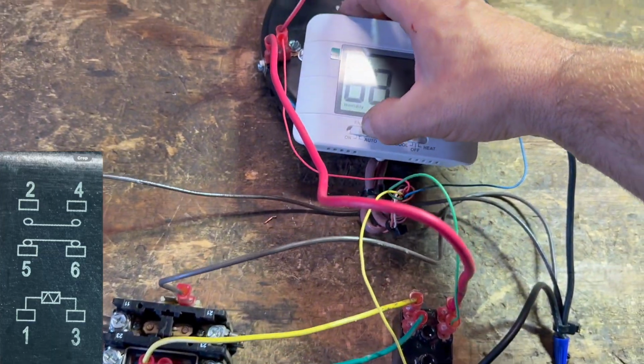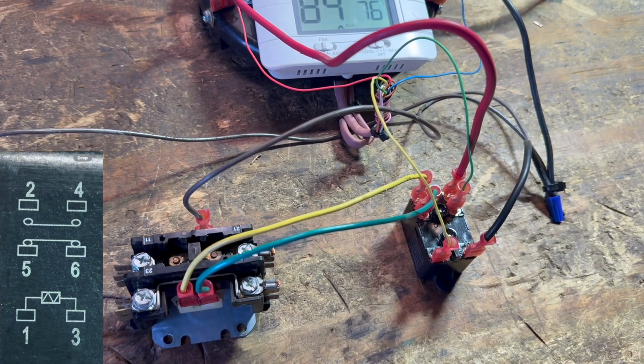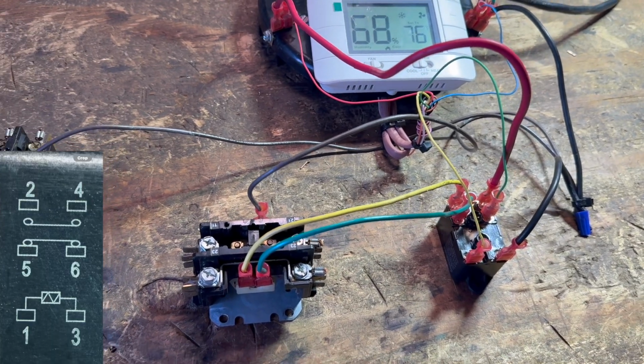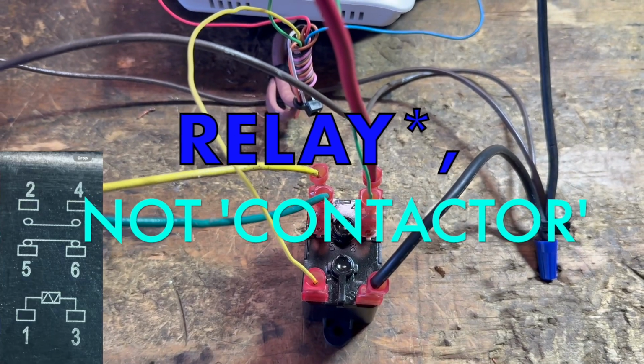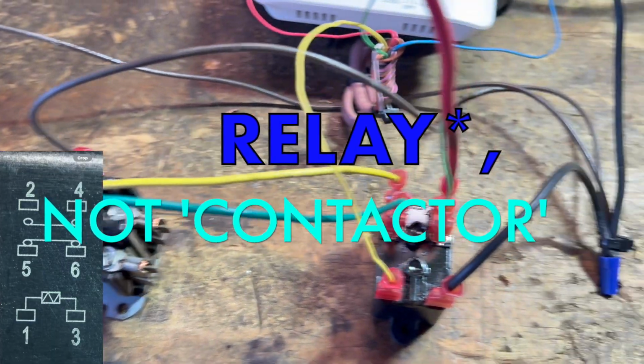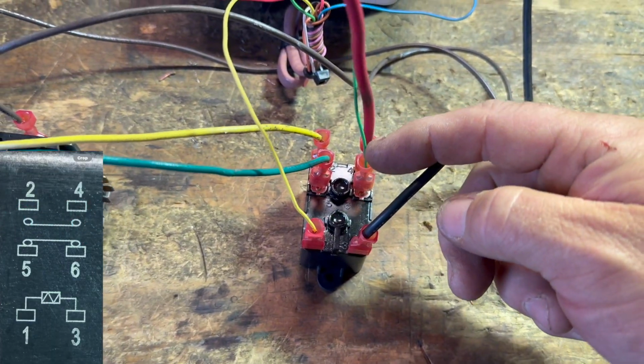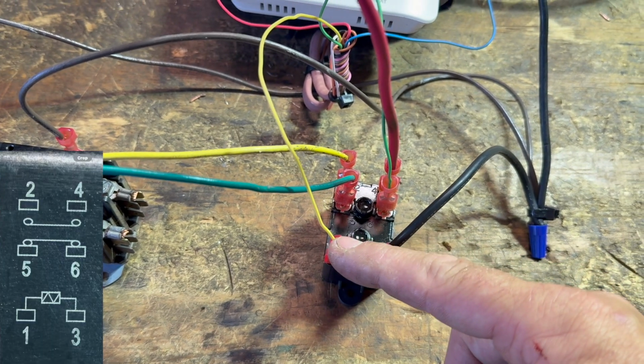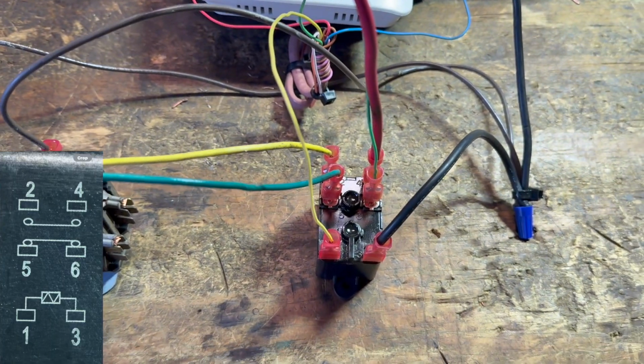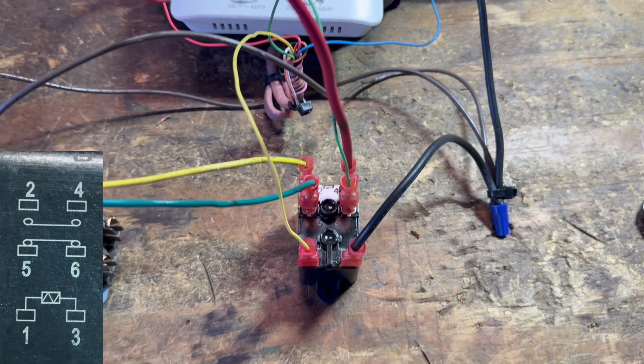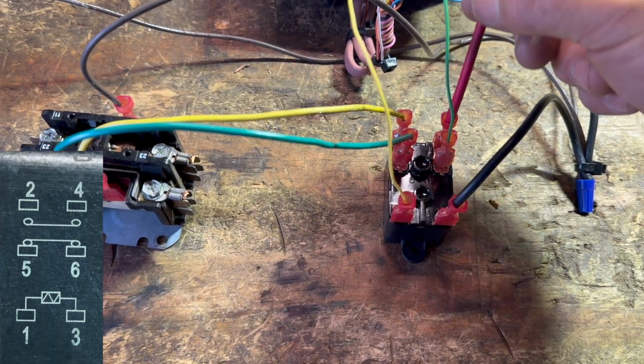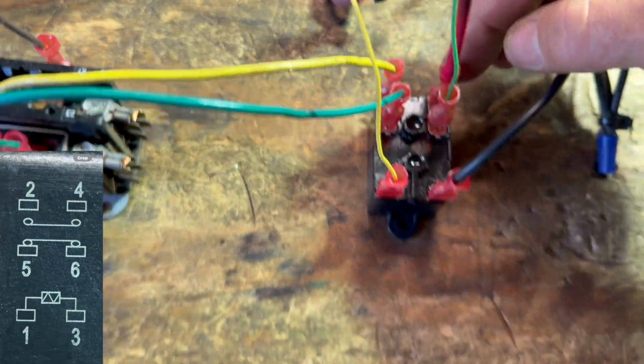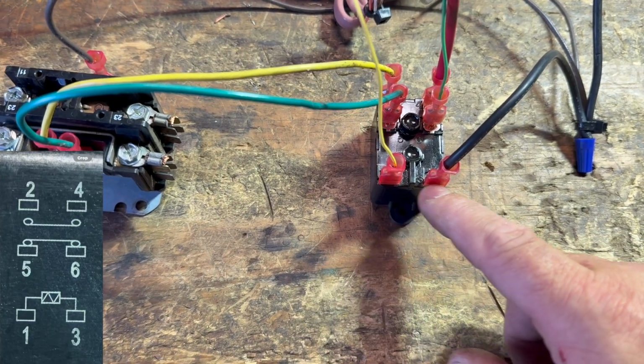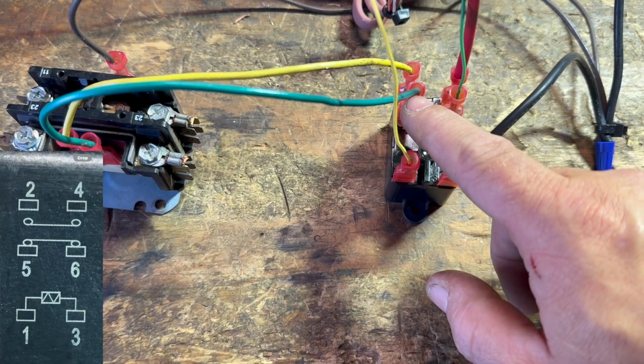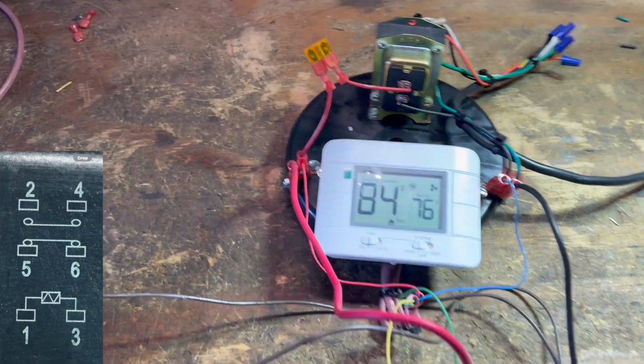Now let's say both are on. Doesn't matter. Again, still have 24 volts going to both. The purpose of the contactor here is that every time we turn on cooling, it's going to turn on the fan. But every time we turn on the fan alone by itself, it will not put 24 volts back into the yellow circuit and therefore not operate the outdoor unit when we don't want it to. So it acts kind of like a little logic circuit that says, if I put in 24 volts here, then we will apply 24 volts to our load through 2 and 4. And if I do not put 24 volts through our load here, I will only apply voltage through 5 and 6. So that's what a relay does.